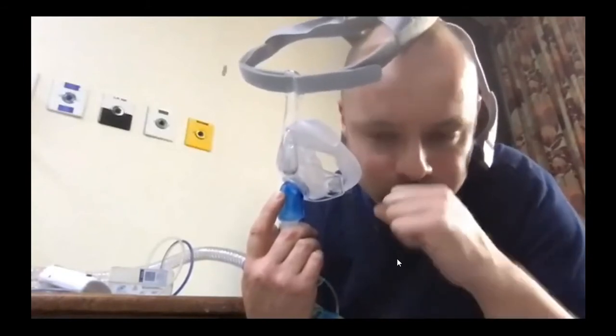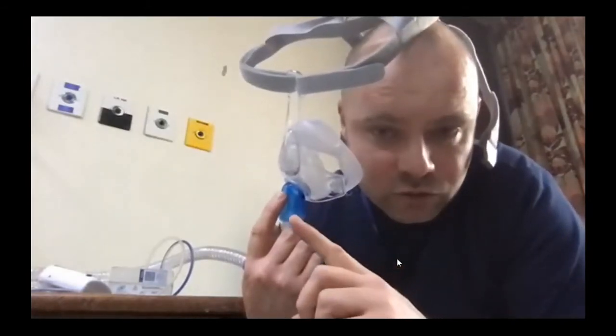What I had found is setting a PEEP value of around 5 to 8 to start with, and then slowly increasing the flow until, A, it's comfortable to breathe, and B, that you can hear any anti-asphyxia valve cycling or entrainment through the side port. You don't want it to be very prolonged, but at peak inspiration, you should be hearing a little bit of entrainment. If there's little to none, you're probably overdoing your flow a little bit and you're just wasting gas.